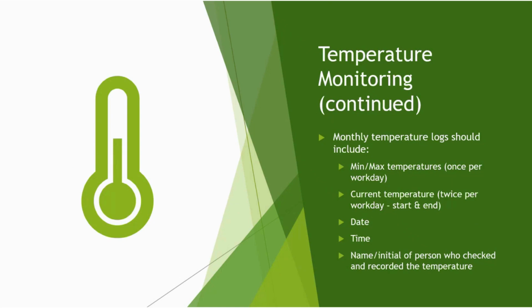The temperature monitoring log should include min-max temperatures once per workday, and should include the current temperature twice per workday, typically at the start and the end of each day. It should include the time, date, and the initial or name of the person who checked and recorded the temperature. These requirements are for those providers who use the typical digital data logger and also the wireless or electronic DDL monitors. Next slide.